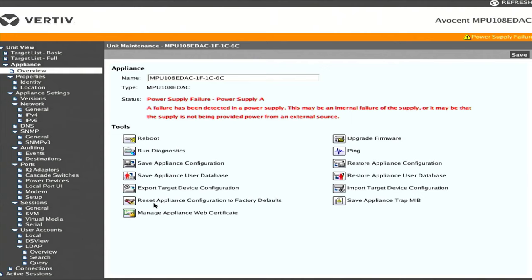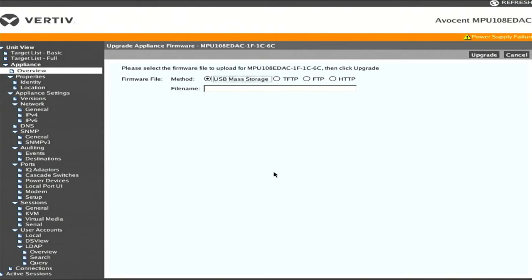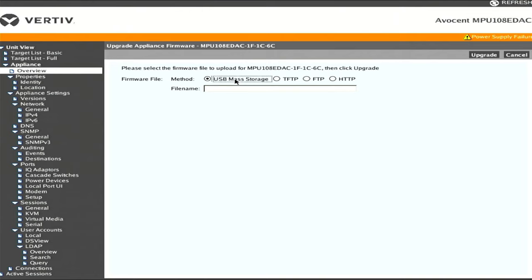I mentioned before I did a factory reset, so that can be done with this option here. Won't go into doing that again, but I want to point out there's also this upgrade firmware option. At the time I got this unit last year, almost exactly a year ago, it was running the original Avocent firmware. I was able to go to the Vertiv website, download the latest firmware, stick it on a USB drive, plug it in and upgrade it. You can also use TFTP, FTP or HTTP, but it's much easier to just use the USB stick.